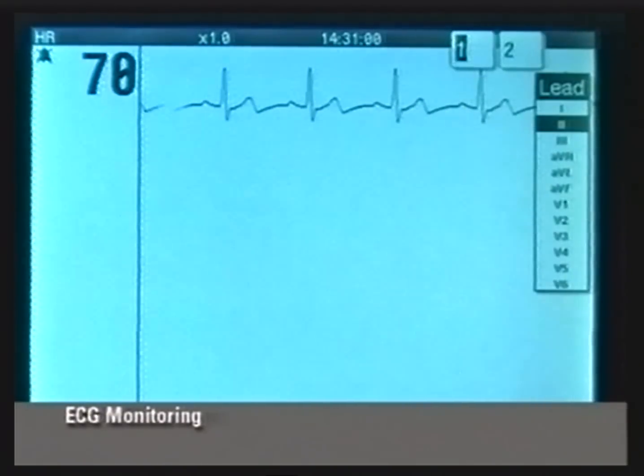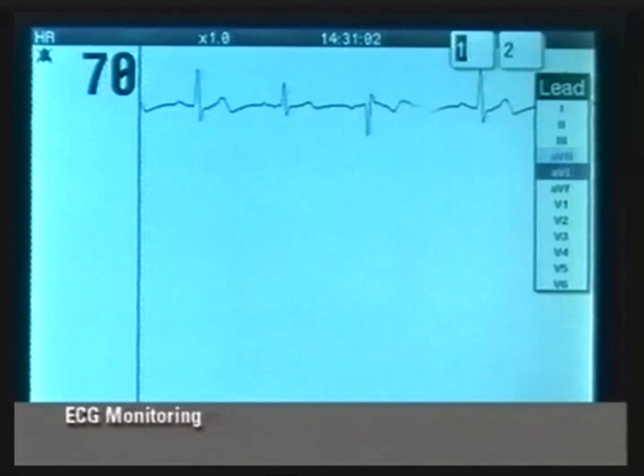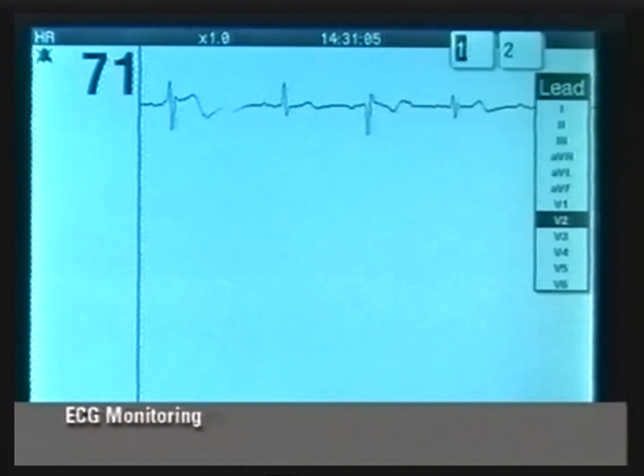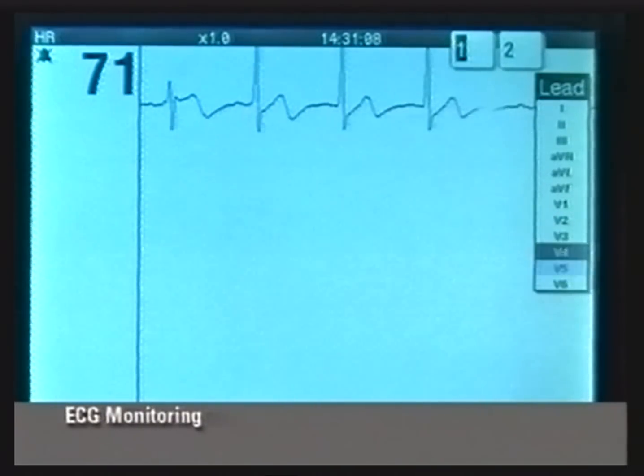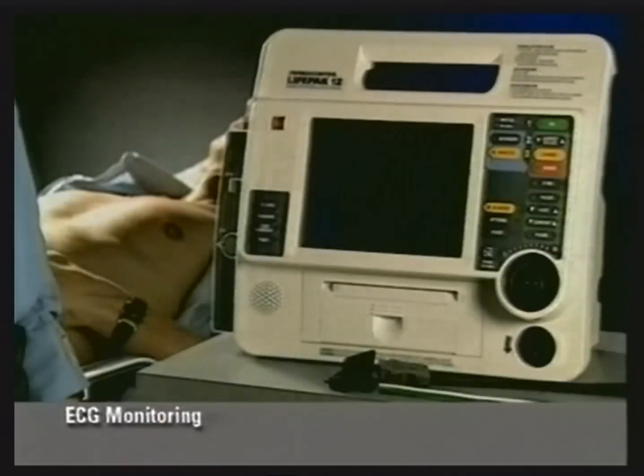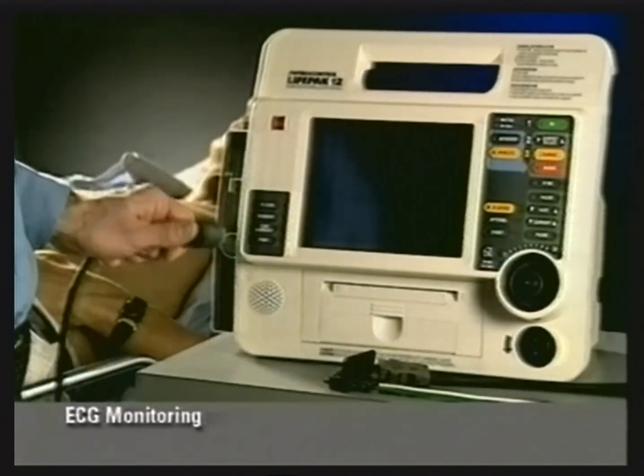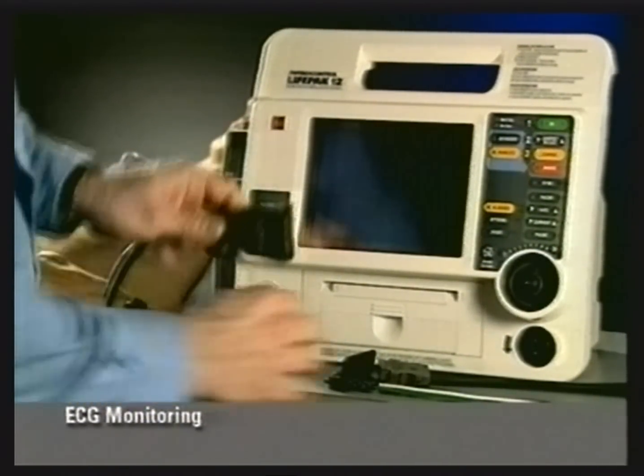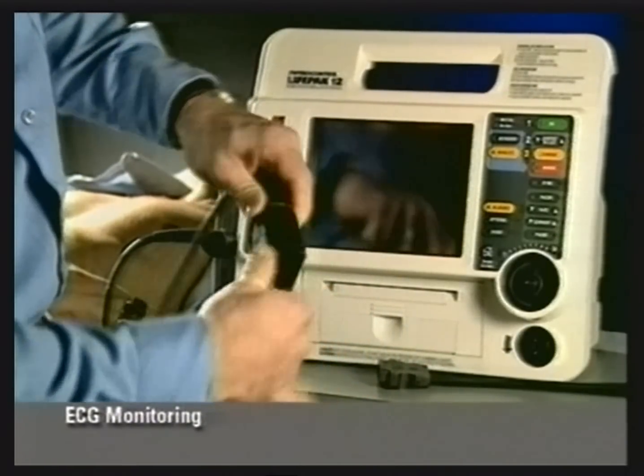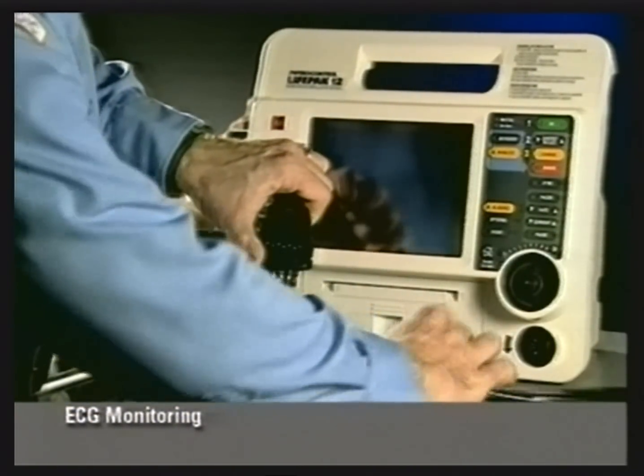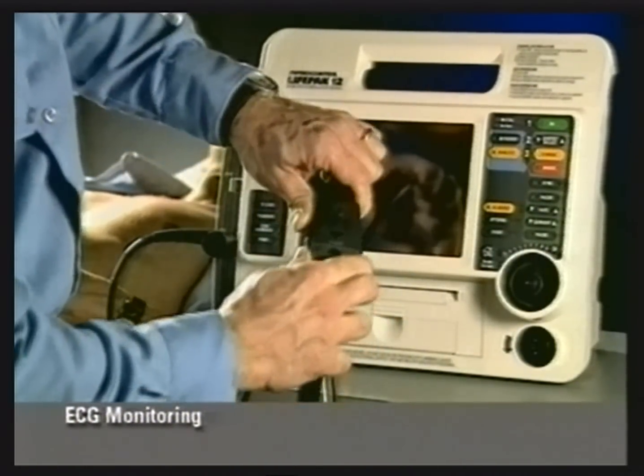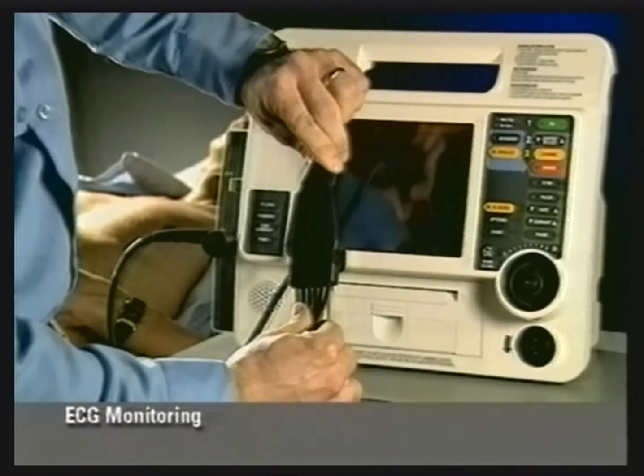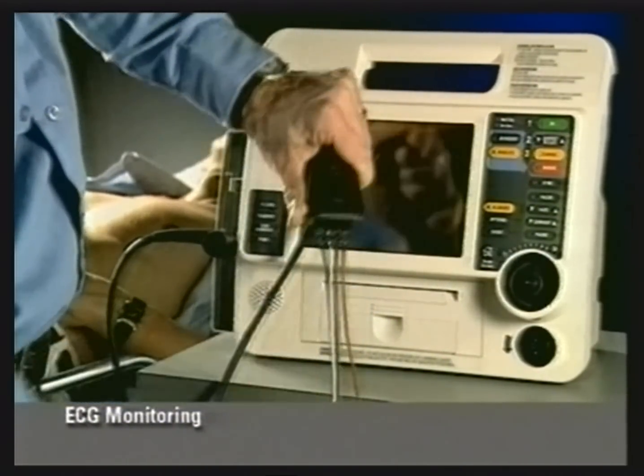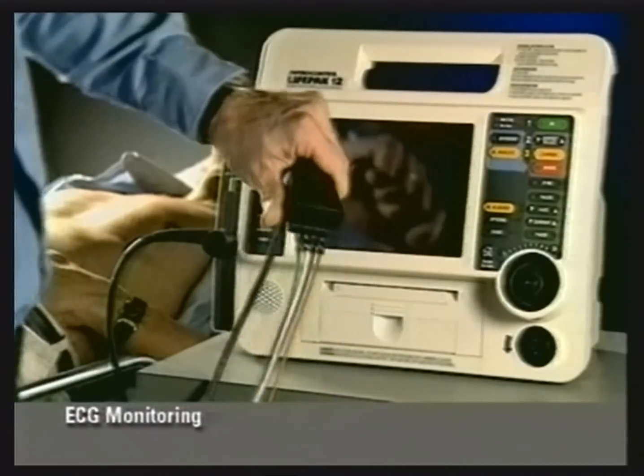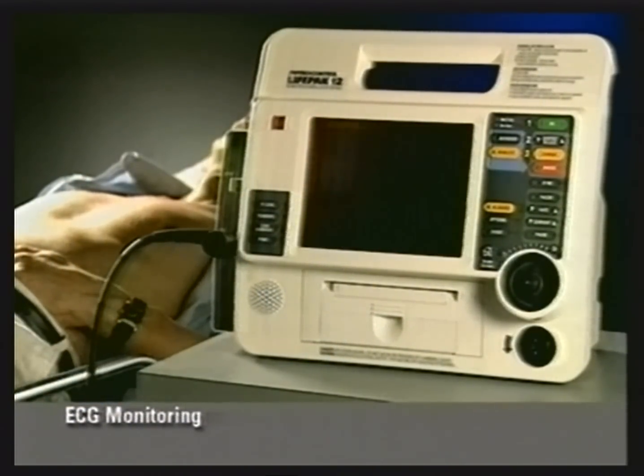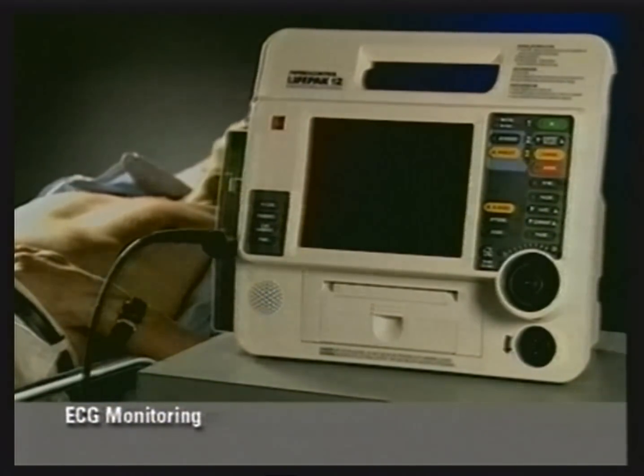When the 12-lead cable is used, the standard limb and precordial leads are available. Only the 12-lead ECG cable will be demonstrated in this video. The 12-lead cable has 3 parts: the main cable that plugs into the monitor, the limb lead attachment that plugs into the main cable, and the precordial lead attachment that also connects to the main cable. The precordial lead attachment is not required for basic ECG monitoring. It is used for precordial lead monitoring or to obtain a 12-lead ECG, which is covered later in this video.